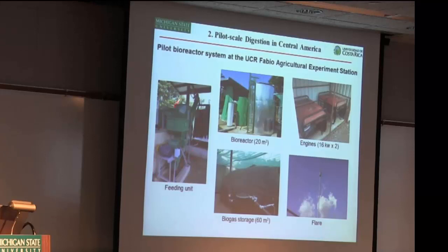We've got a grinding apparatus, so our feedstock comes in, and the feedstock in this case is a mix of chicken manure, dairy manure, and whatever fruits and vegetables are available from the local packing house. You may have whole bananas, pieces of papaya and mango, but everything goes through a hammer mill to break those particles down. One of the keys to biological conversion is providing surface area for the microorganisms to work. So generally we're trying to grind or chop materials as fine as possible, and a hammer mill gets us relatively fine. I think our screen size was about 3/16 of an inch, so we were able to shred material pretty well.